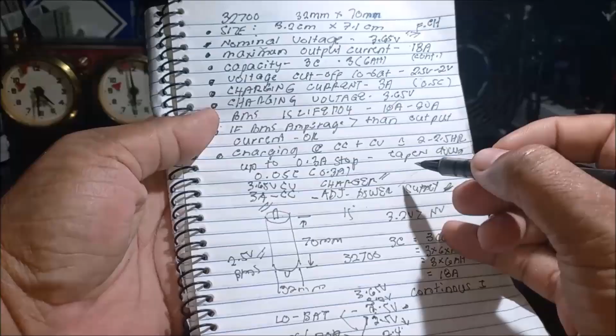So here you can see we are charging at 3.65 volts at 3 ampere charging current: constant current 3 ampere, constant voltage 3.65 volts. It will stop at 0.05C. Our capacity C is 6,000 milliampere hour, and multiplying that by 0.05 gives 0.3 ampere. So when the battery reaches 0.3 ampere during charging, it will stop.